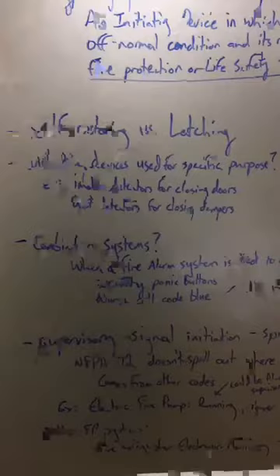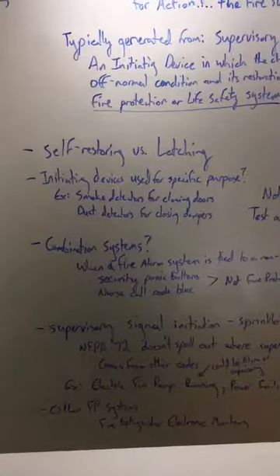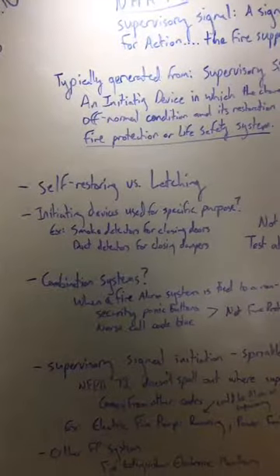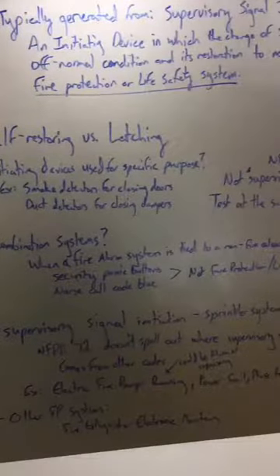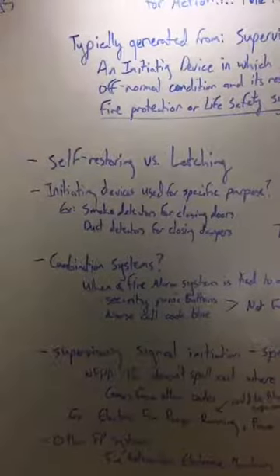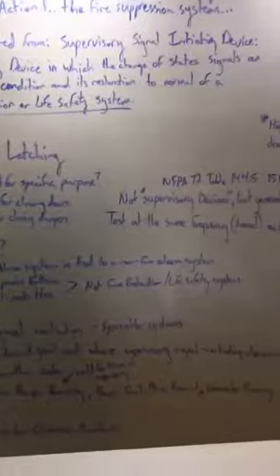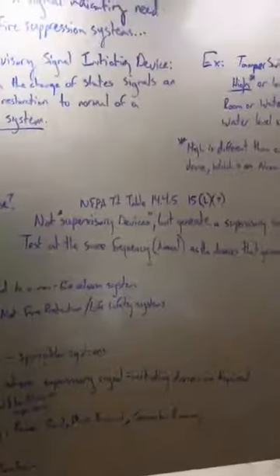So what about initiating devices that are used for specific purposes in code? Code allows us to have smoke detectors for closing doors, duct detectors for closing dampers. It's not required to trigger the fire alarm system. It can trigger a supervisory signal at a constantly attended location. But what about those? Well, NFPA 72 does clarify that for us.